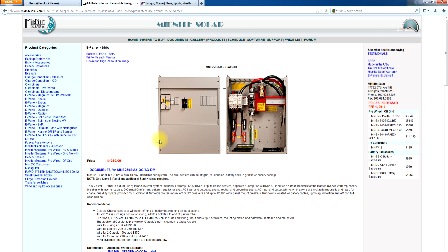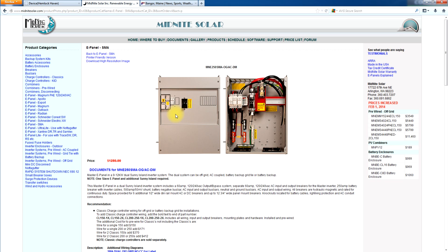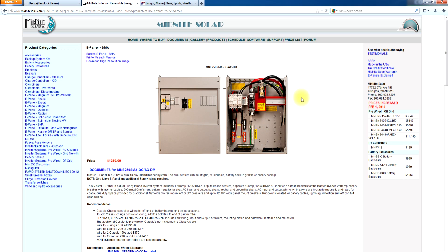And then we go to the off-grid AC dual master. So what this is is a dual master e-panel. This e-panel is intended for a scenario where you're using two Sunny Islands. You would need a slave e-panel over here on the right or on the left, whichever side you decide to put the slave on. But this e-panel has the bypass for 240 volts. As you can see it's got the red and black bus bars for in and out. And it has the breakers for this Sunny Island. And of course the slave e-panel would have the two breakers in the red wire for the slave Sunny Island, which would then wire over to the input bus bars here.